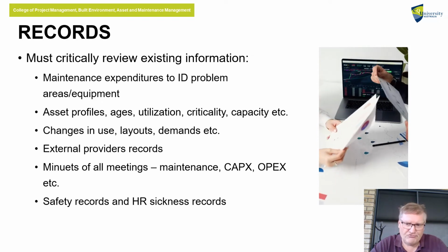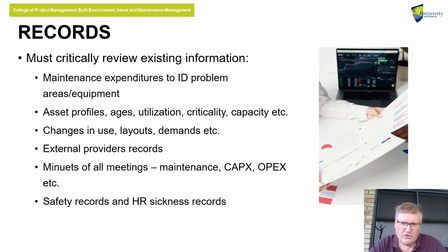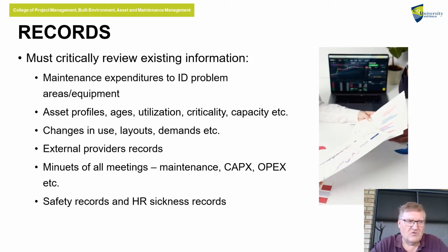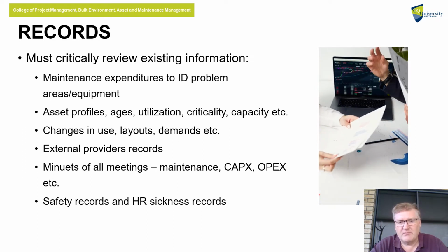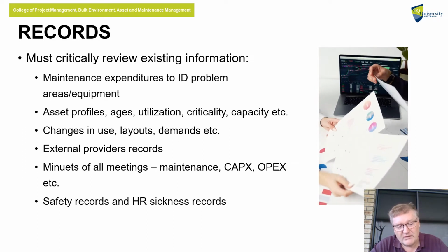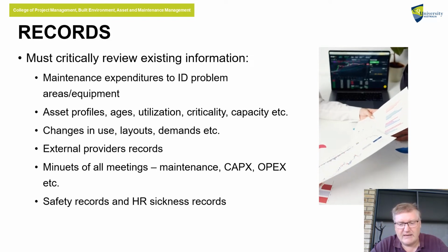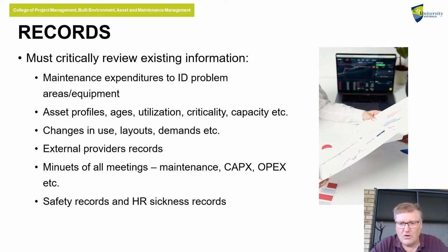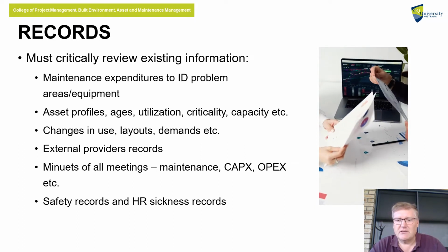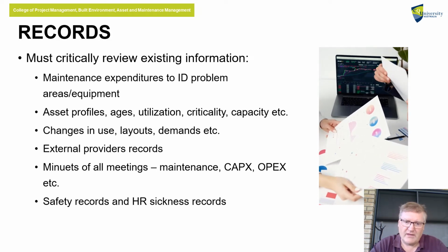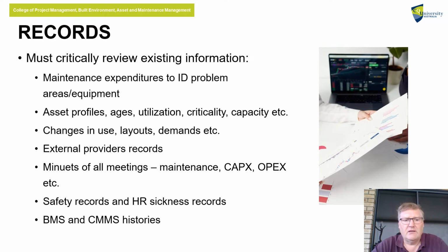Now this was stripped of any identification. I got HR to strip identification of who the people were, what they did or anything. You could draw some conclusions where the clusters were because that was a certain business unit maybe, but that allowed us to track down which air conditioning ductwork and which chiller set and which compressors, etc., were causing the hotspots, and they were replaced and the hotspots disappeared. So you can do that. That's only an example. It would be different for whatever industry you're actually in.